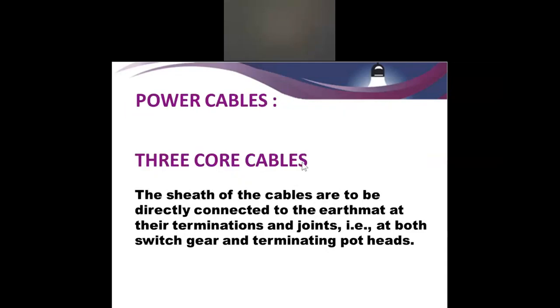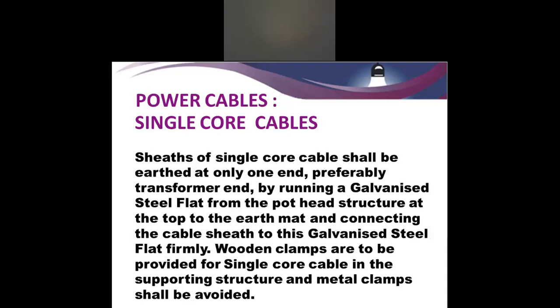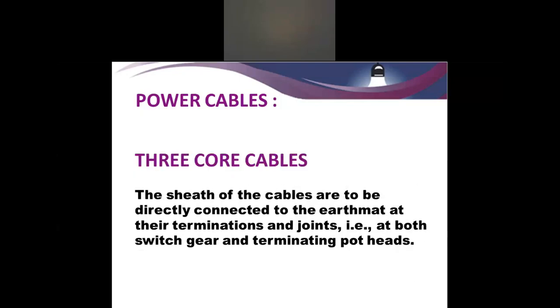Coming to power cables, there are 3-core cable and single-core cable. Most of the practice we normally do is connect both ends, because cables come with earthing options at both ends, and we tend to connect both ends of the 3-core cable and single-core cable together. But whenever we connect both ends of a single-core cable, it will create a path for current to flow, and that will cause damage to the cable. So for a single core cable, it should be connected at one point, and for a 3-core cable, both ends should be connected.